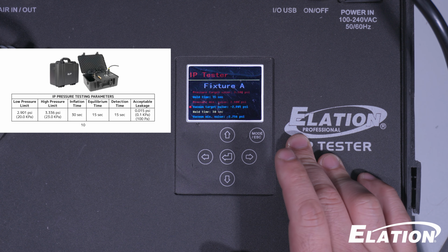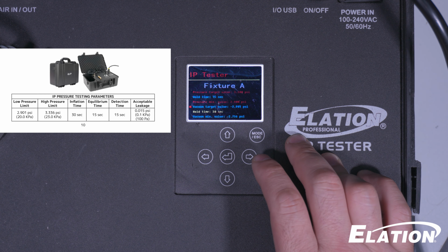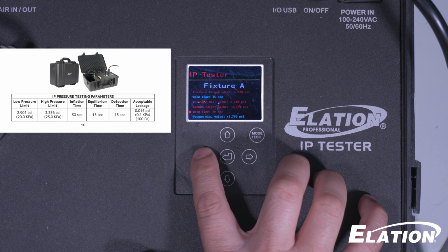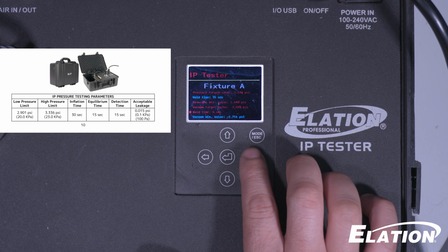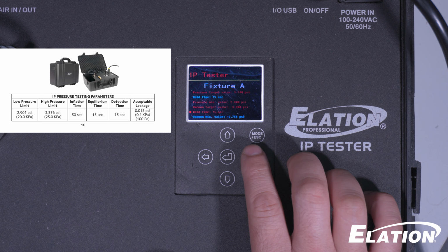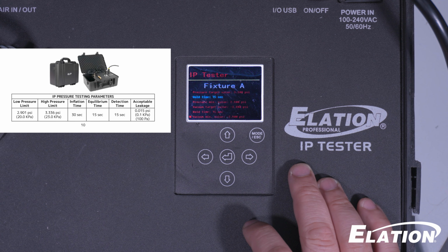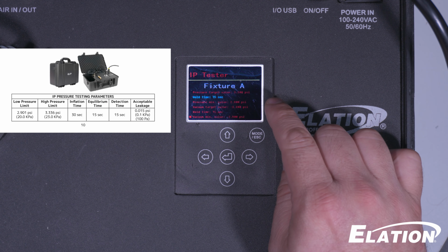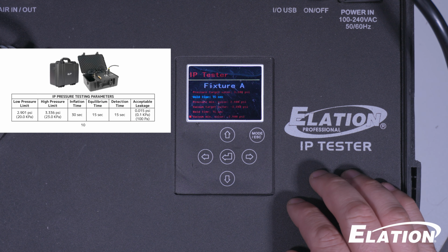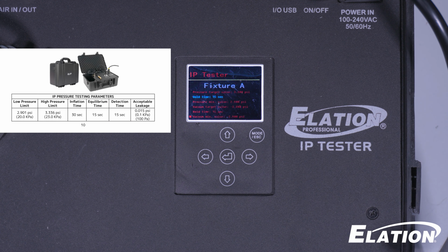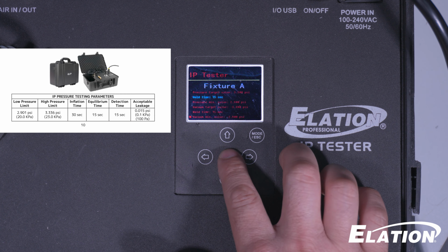And then it's just going to be opposite. Well, in the negatives for when it comes to the vacuum, we're going to put the 3.3 and then the hold time for 15 seconds. Oops, too far. And then again, we're going to do the 2.9. So here you could see that we have the 3.3, which is the target pressure. Then we have the minimum, which is the 2.9. And then pretty much negatives for the vacuum, which is going to be the negative 3.3 at 15 seconds and the negative 2.9. We're going to go ahead and push enter.